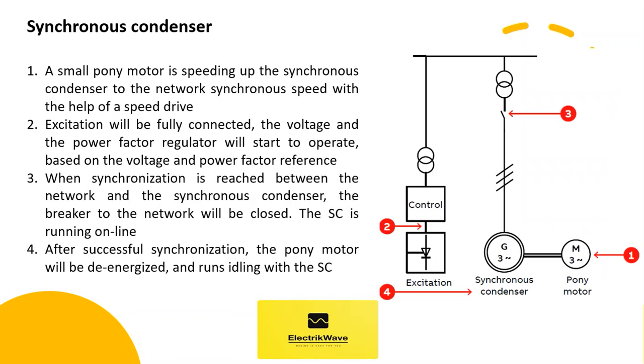This is the single line diagram for synchronous condenser connectivity arrangement. Item number 1 is the pony motor. The pony motor and VSD will ramp up the speed of the synchronous condenser to synchronous speed, after which the synchronous condenser will be synchronized to the grid and the MVCB is closed. After that, the pony motor is only used during the short starting procedure of the synchronous condenser.